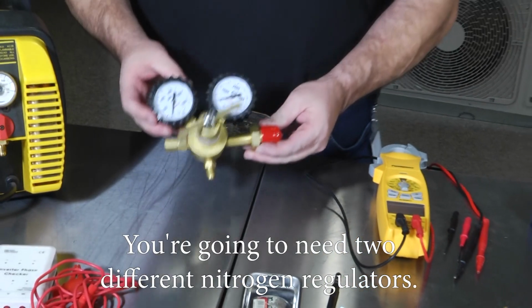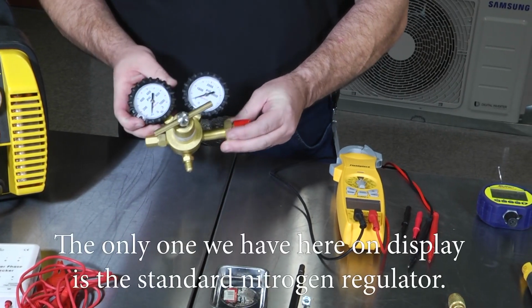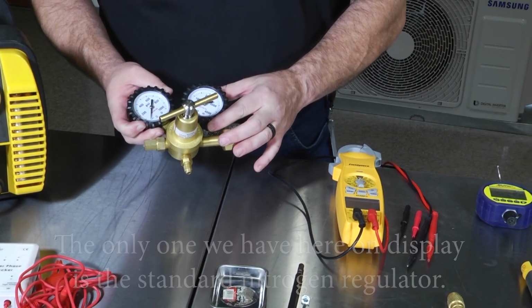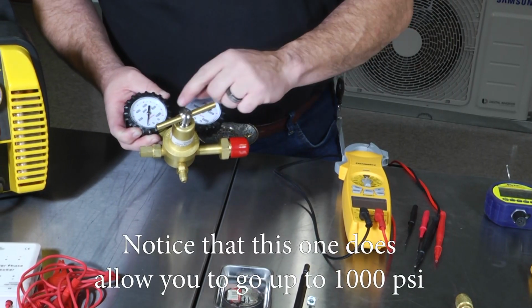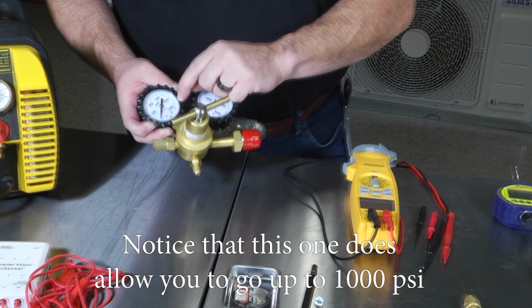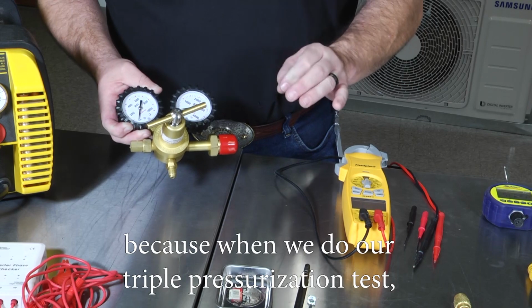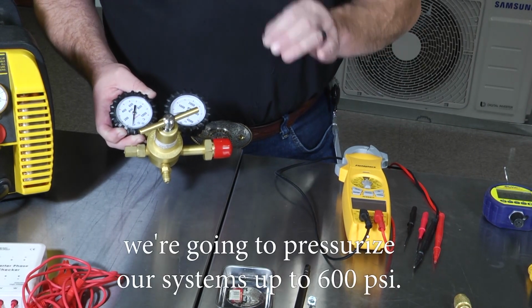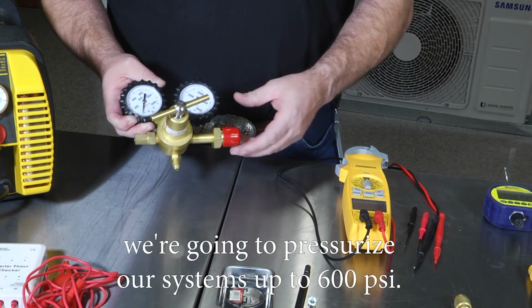You're going to need 2 different nitrogen regulators. The only one we have here on display is the standard nitrogen regulator. Notice that this one does allow you to go up to 1,000 psi, because that's when we do our triple pressurization test. We're going to pressurize our systems to up to 600 psi.